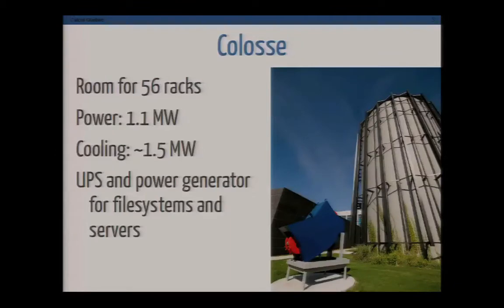Colosse is the name of our system. It's an old particle accelerator that was used for a couple of years, and we recycled it into a data center. It's pretty different from what we usually see — it's a circular model with 56 racks, about one megawatt of power and cooling, and UPS and power generator for the management nodes and the file system.